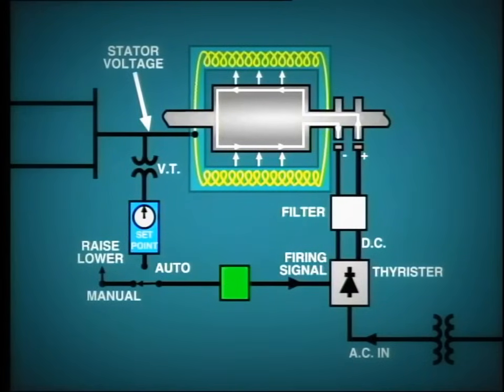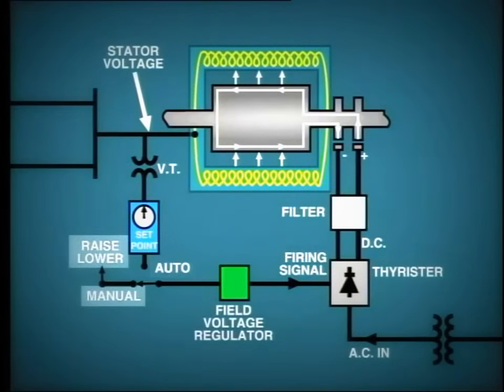The firing circuit is controlled by the field voltage regulator. This regulator has two inputs, manual and auto. The manual control disconnects the automatic function and allows the operator to directly control excitation.